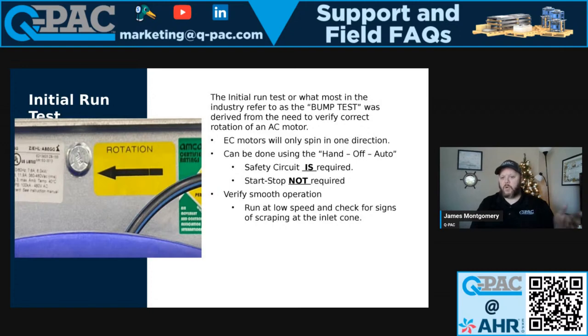We already checked that before, but we're checking it again. Make sure none of the cables are somehow coming in contact with the blades. Make sure there's nothing left in the unit that can get sucked in, pushed out, or blown around. I mean, obviously, these are times where you've got to take safety precautions, but it's a smooth operation. We're listening for that inlet cone to be rubbing, so see if we need to adjust it.